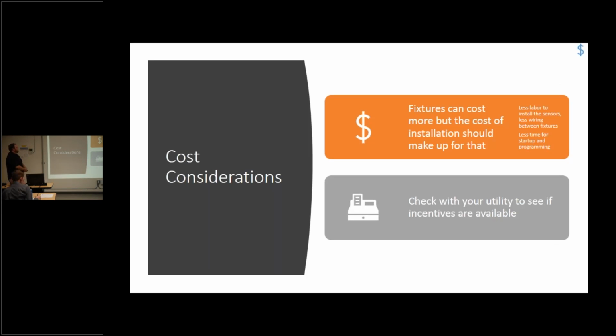As for cost considerations: fixtures can cost more, but the cost of installation should make up for that—less labor to install the sensors, less wiring between fixtures, less time for startup and programming, because with a network gateway LLLC you can do it remotely, telling the fixture its program, downloading and updating it, and so on. Check with your utility provider to see if incentives are available. I currently don't know of any Idaho Power incentives specifically for Luminaire level lighting controls, but if you'd like to see them, ask them for it.